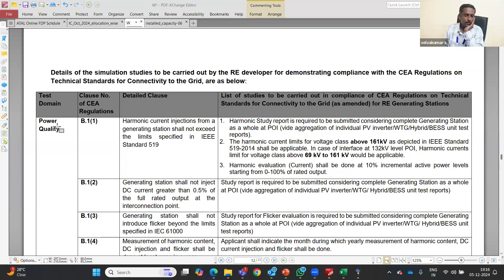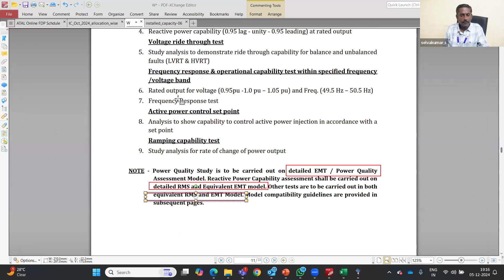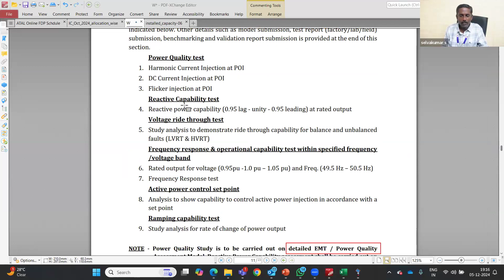So as a part of the grid compliance study, the first topic which you need to focus on is power quality. First, harmonics, DC current injection, flicker. Three things which you need to do. For harmonics, you have to follow the standard IEEE 519. IEEE 519 gives the limits for the voltage as well as the current harmonics, how much can be injected to the grid at various voltage levels.